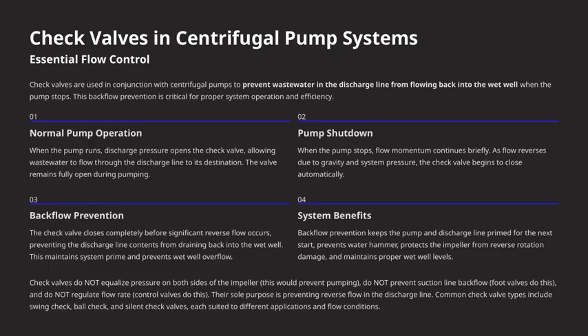Now, let's talk about check valves in centrifugal pump systems and why they are so essential for flow control. Check valves are used alongside pumps to prevent wastewater in the discharge line from flowing back into the wet well when the pump stops. This backflow prevention is critical because it ensures the system operates correctly and maintains efficiency. When the pump is running, the discharge pressure opens the check valve, allowing wastewater to flow smoothly through the discharge line to its destination. During this time, the valve remains fully open, facilitating continuous flow.